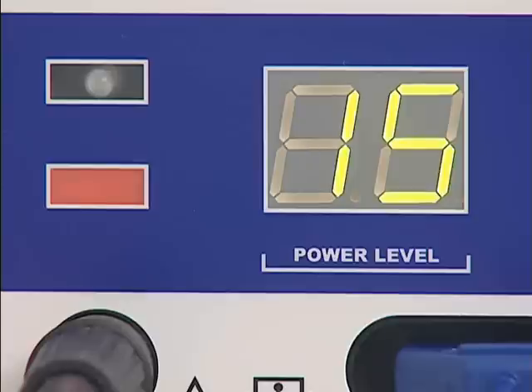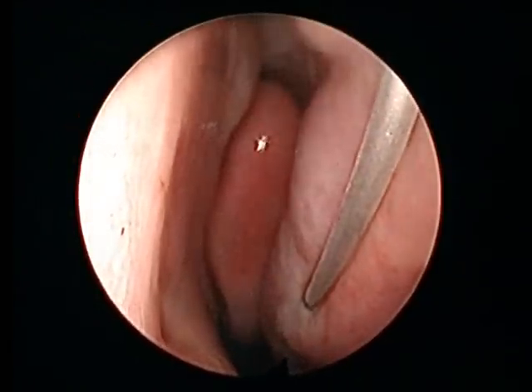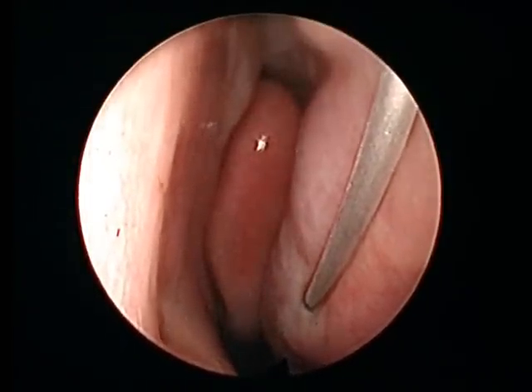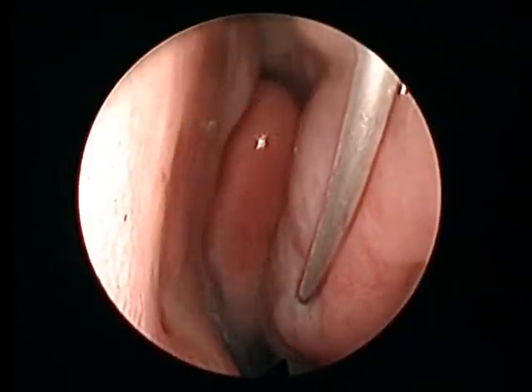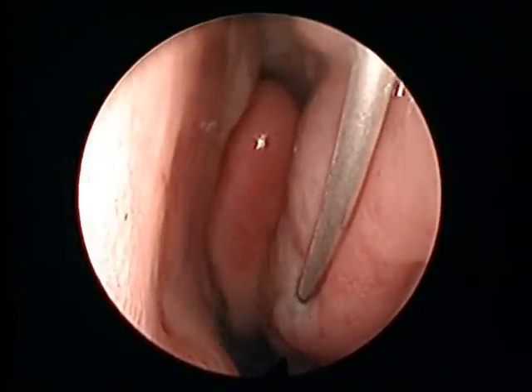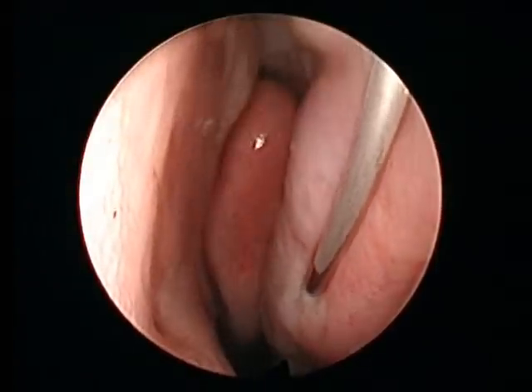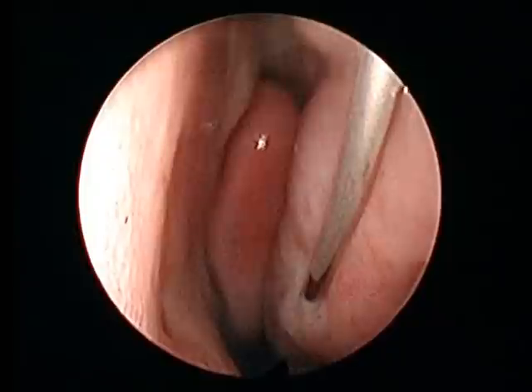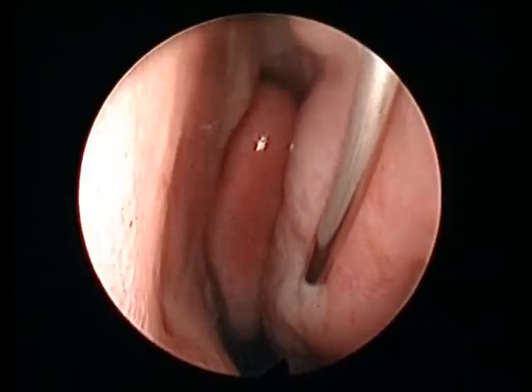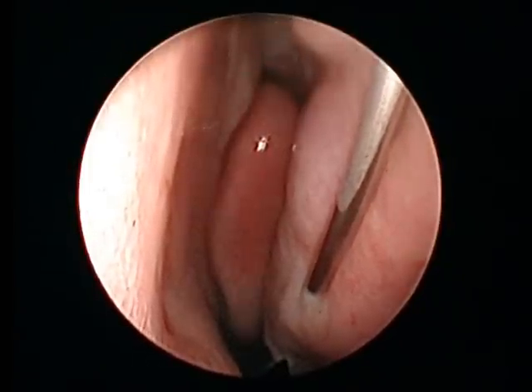Once the applicator has been positioned, the power supply is activated by pressing the foot switch. The status of the coagulation can be monitored via the acoustic signal. An increasing pitch of the signal indicates the progress of coagulation and the increasing tissue impedance. The power output is controlled automatically. A high-pitched intermittent signal indicates the completion of the coagulation process. The power output is reduced automatically so that overdose effects are excluded.